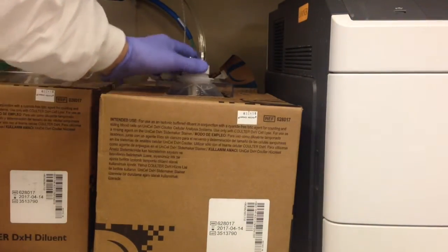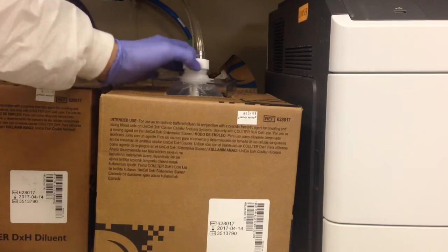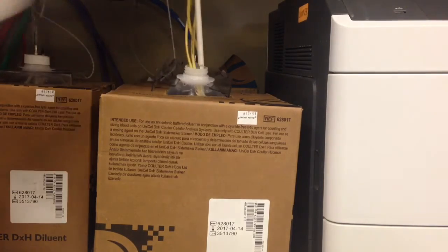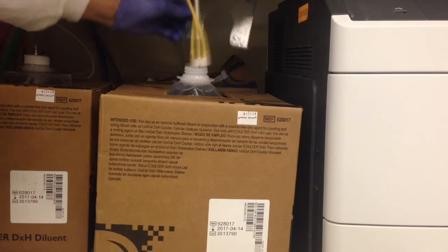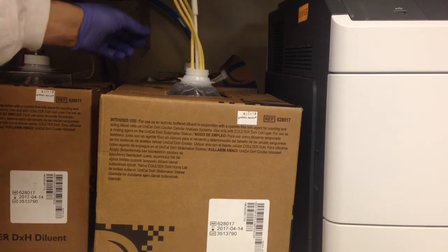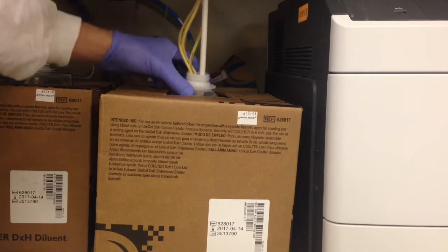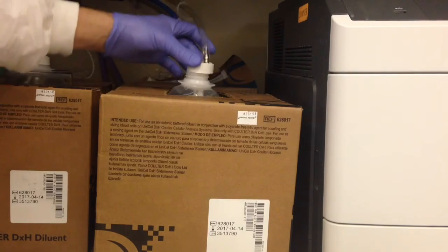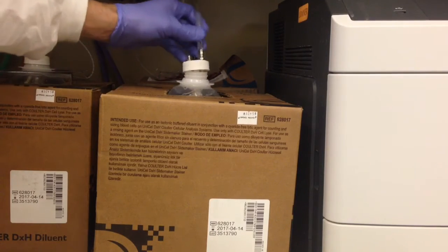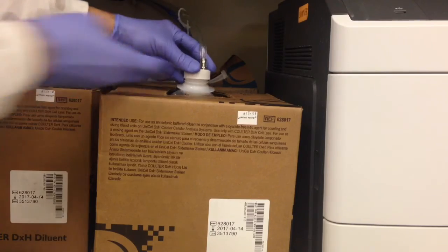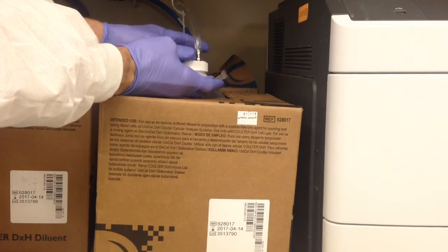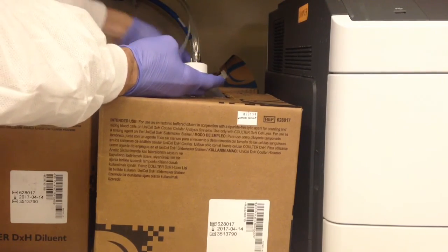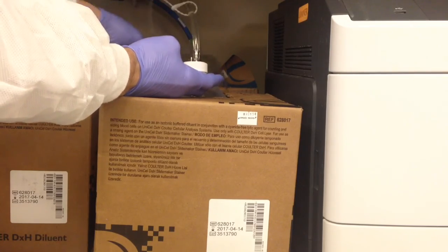Also up here, it's where the tubing goes in. It's pretty easy. It's just a little screw top. And then there's actually a plastic cover piece that's supposed to hold the reagent from collapsing in on itself. I try and screw this in with just one hand, which is a little awkward, but it's just a screw. It's very easy. And then once you get the tubing attached to the top of the reagent, you just go ahead and place that plastic cover in place. It just kind of slides on. And that's all you have to do there.